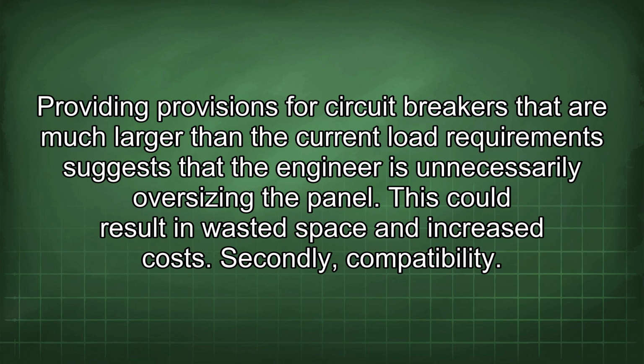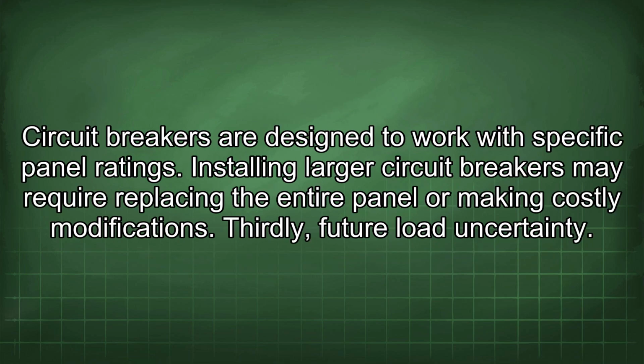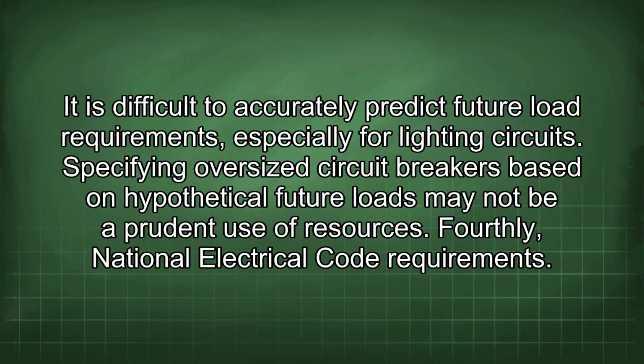Secondly, compatibility. Circuit breakers are designed to work with specific panel ratings. Installing larger circuit breakers may require replacing the entire panel or making costly modifications. Thirdly, future load uncertainty. It is difficult to accurately predict future load requirements, especially for lighting circuits. Specifying oversized circuit breakers based on hypothetical future loads may not be a prudent use of resources.